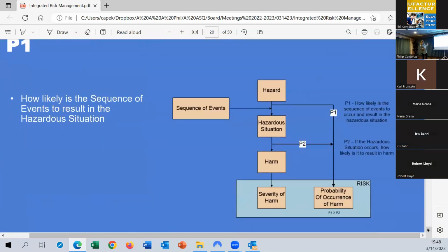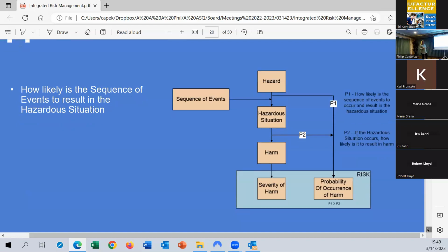And now the P1, the likelihood that that sequence of events results in the hazardous situation, which is the second component of our probability of occurrence of harm, this is what we can affect, right? When we apply controls, we're reducing the probability that that sequence of events results in that hazardous situation. And this is where we actually focus most of our attention in risk management.